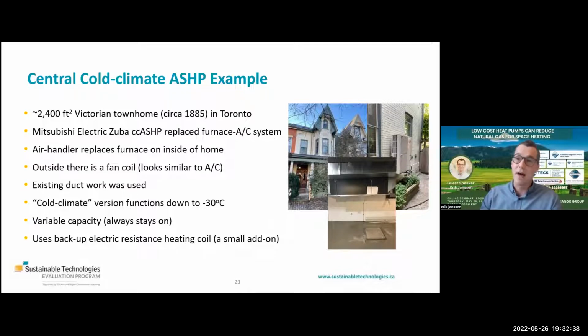It did require her to have an electrical service upgrade to her home as well. She has a cold climate version, which is almost a slang term meaning it can continue to function in really extreme cold conditions. The latest equipment from Mitsubishi, Daikin and other manufacturers operates down to -30 Celsius. It's not terribly efficient at that temperature, but it's still pumping heat above a COP of 1 at really cold temperatures. The unit is also variable capacity, meaning it's essentially always on, just modulating its heating output to the heating requirements of the home.